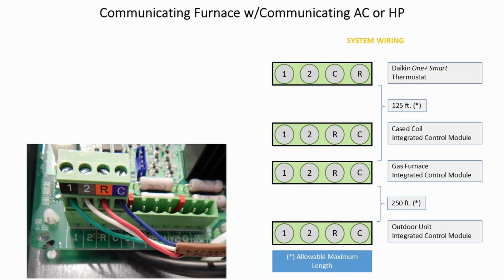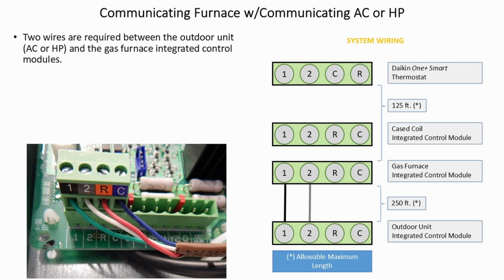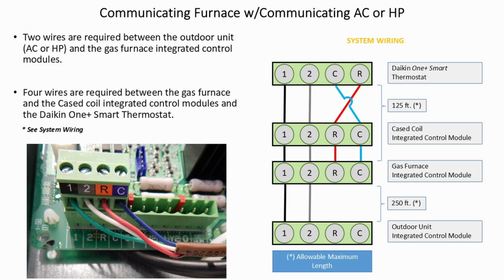Communicating furnace with a communicating air conditioner or heat pump. 2 wires are required between the outdoor unit, air conditioner or heat pump, and the gas furnace integrated control module. These wires are for communication only and will be connected between the outdoor unit and the gas furnace on terminals 1 and 2. 4 wires are required between the gas furnace and the cased coil integrated control modules, and the Daikin One+ Smart Thermostat. R and C are for power, 1 and 2 are for communication.